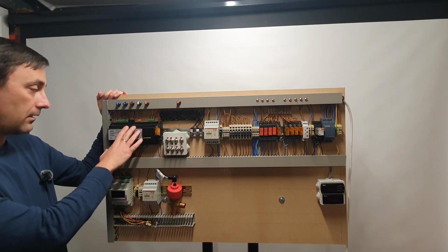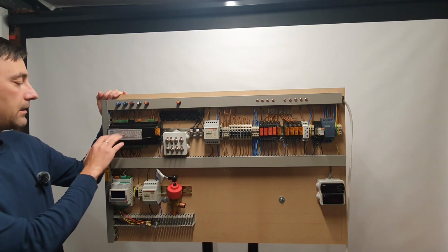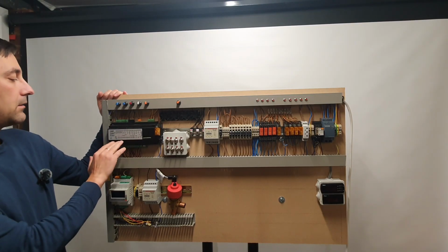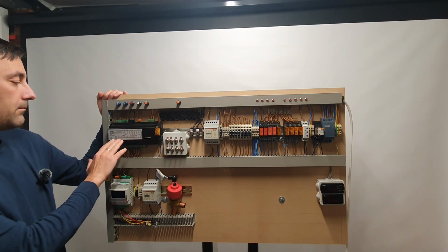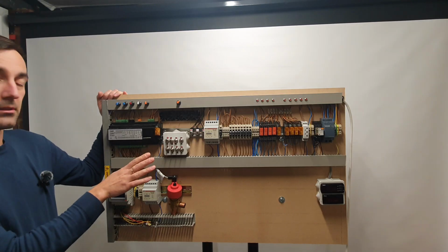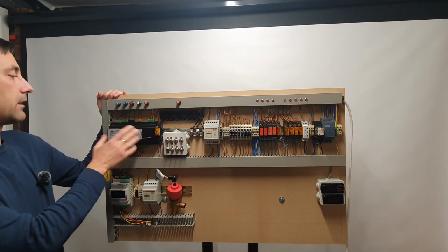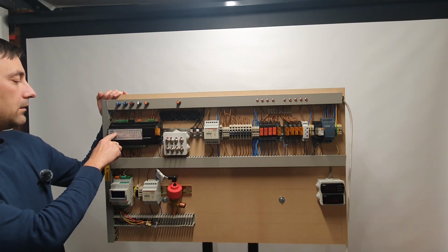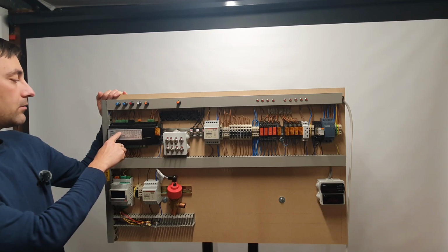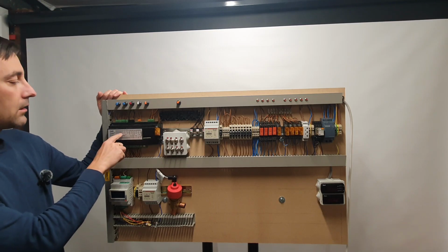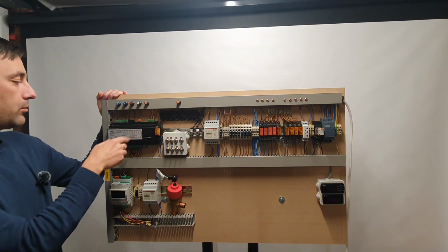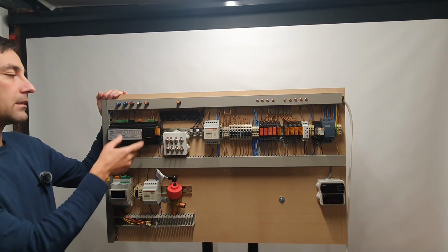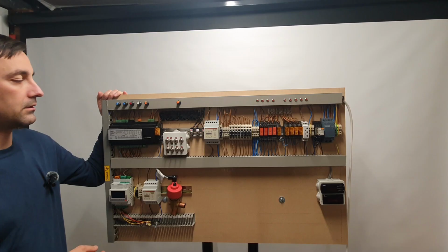I've used a Danfoss pack controller, an EKC 531B, which can deal with up to 10 compressors, and obviously recognizes the safety trips on the compressor side. It's got a 0 to 10 volt output for the condenser fans, plus many other features which we will explore in future videos.